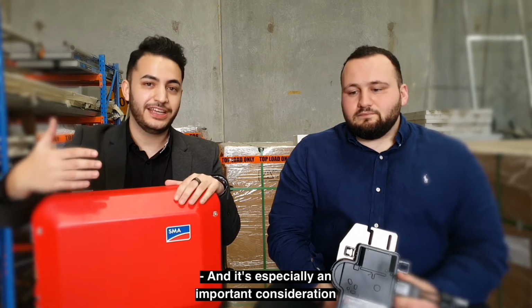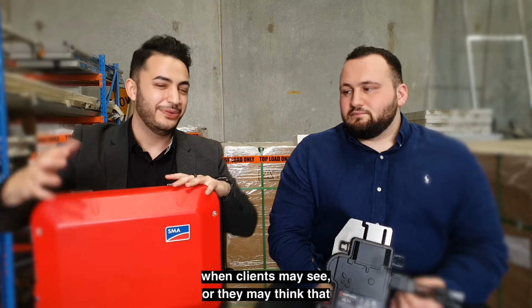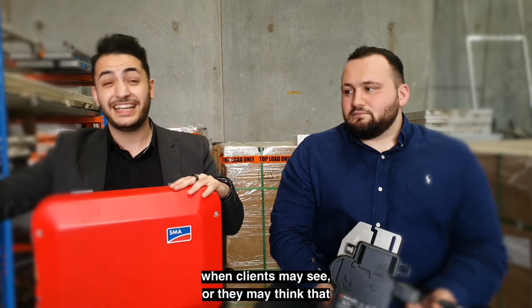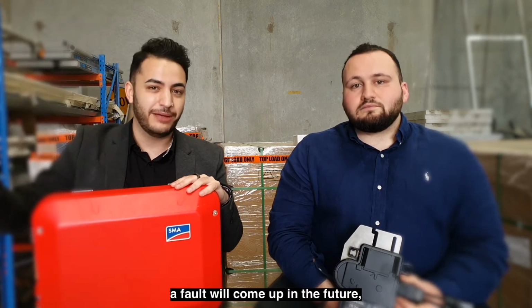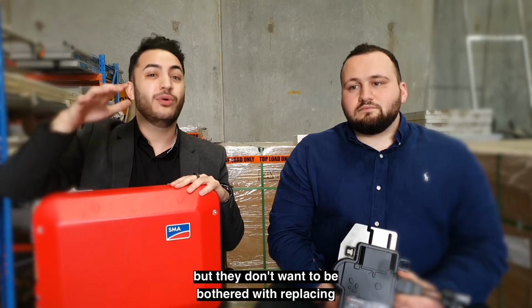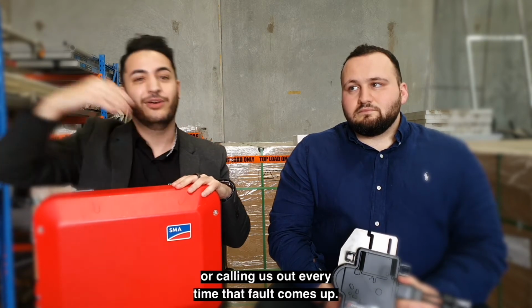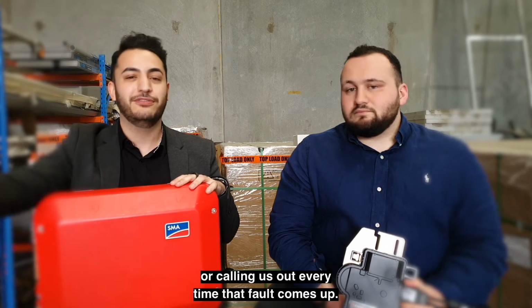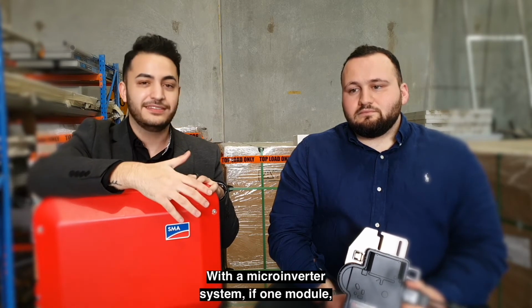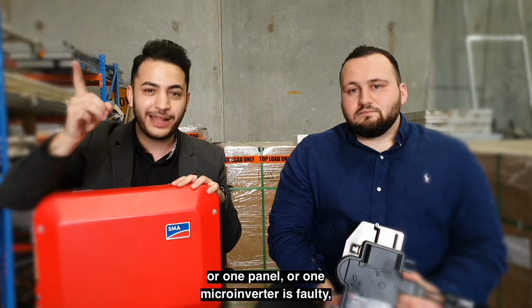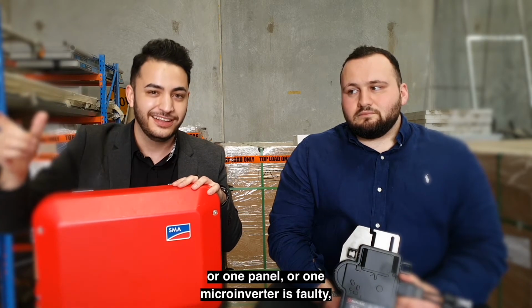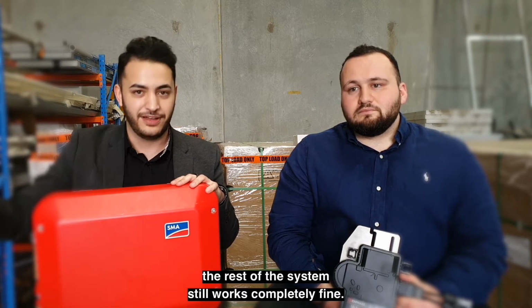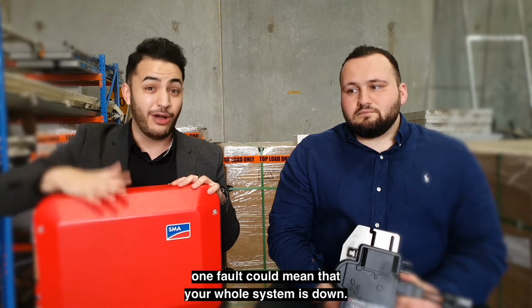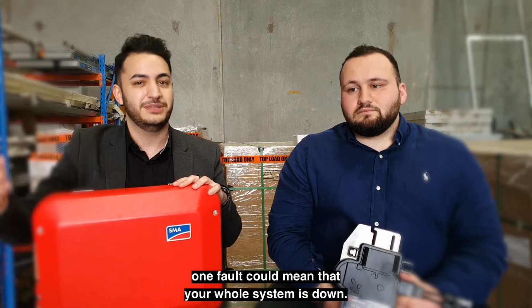This is an especially important consideration when clients think that a fault will come up in the future, but they don't want to be bothered with calling us out every time that fault comes up. With a microinverter system, if one module or one microinverter is faulty, the rest of the system still works completely fine. Whereas with a string inverter, one fault could mean that your whole system is down.